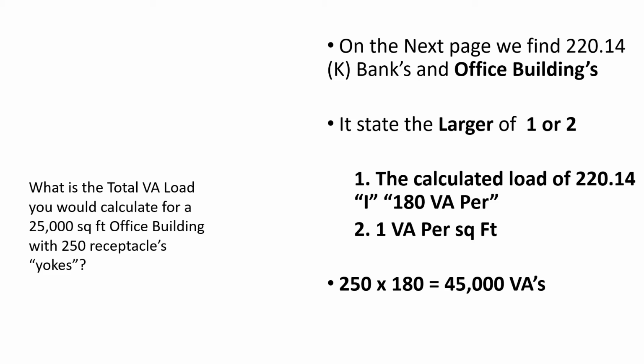First we have to calculate the totals of both. We take 250 receptacles multiplied by 180, and that is going to give us 45,000 VAs. Then we also take the 25,000 square feet, multiply it by 1 VA per square foot, and that is going to give us 25,000 VAs. But we cannot stop there.